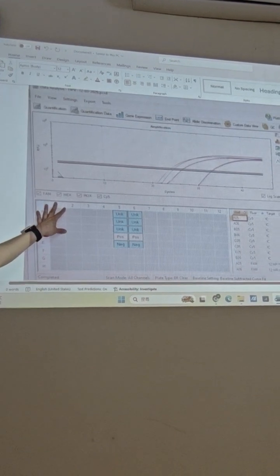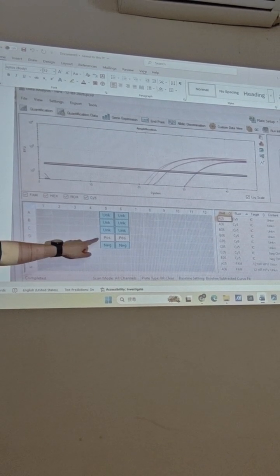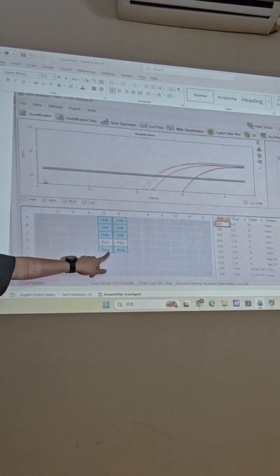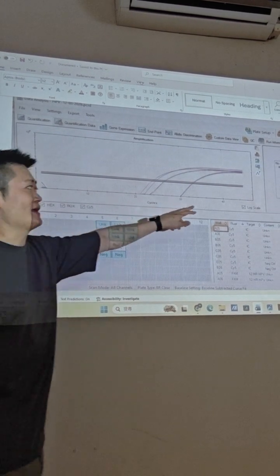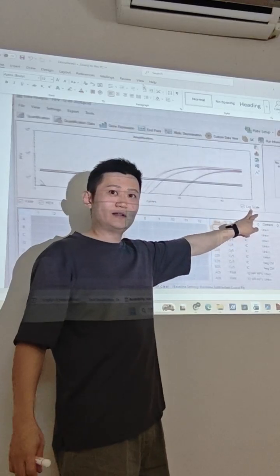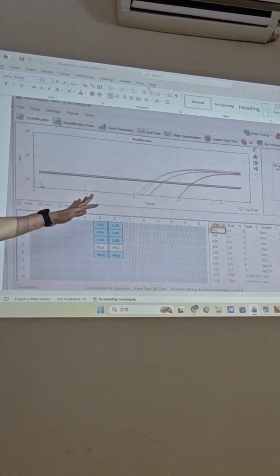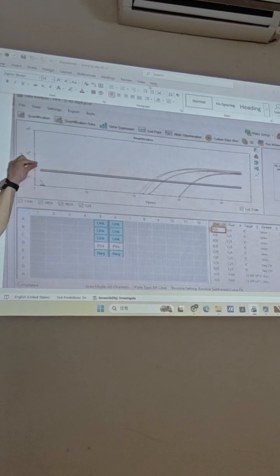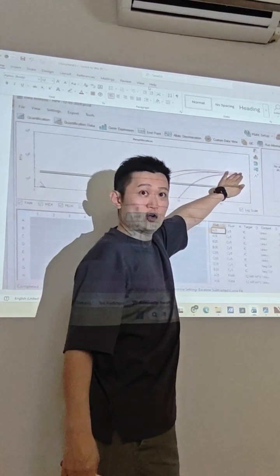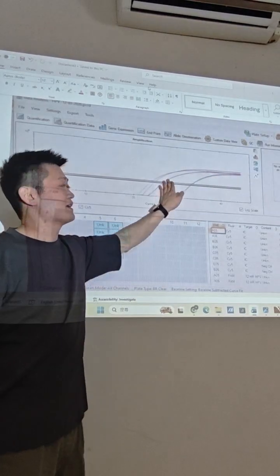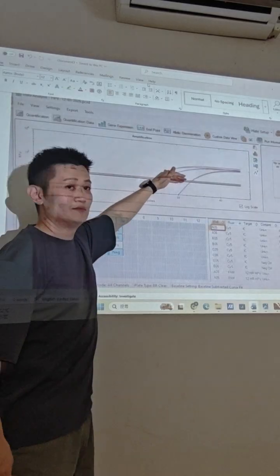So normally for the adjustment, you don't need to click the positive; you just use the negative and the sample. And then you click the log scale. After you click the log scale, you will see something like this. So you set the line between the plateau and the amplification log, in the middle.